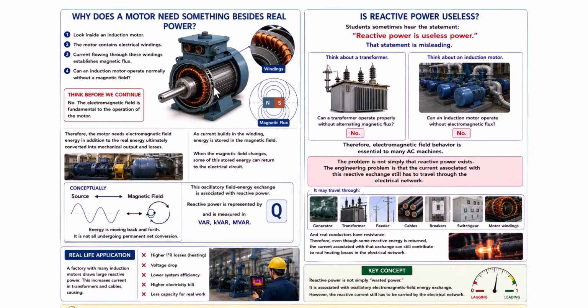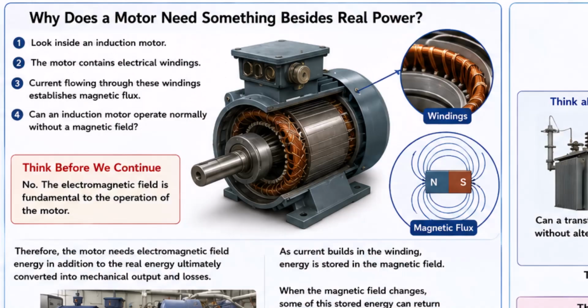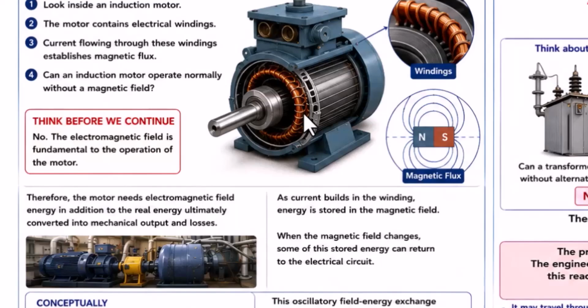Why does a motor need something besides real power? Look inside an induction motor. The motor contains electrical windings. The current flowing through these windings establishes a magnetic field. Think before we continue. Can an induction motor operate normally without a magnetic field? No. The electromagnetic field is fundamental to the operation of the motor. Therefore, the motor needs electromagnetic field energy in addition to the real energy ultimately converted into mechanical output and losses.